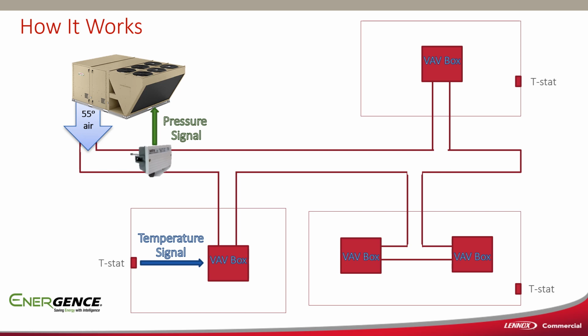While that's happening, we are going to supply 55-degree air out of the package unit, utilizing what we call discharge air control. So our compressors are going to stage up and down whatever they have to do to meet 55-degree discharge air that's being measured in the supply trunk leaving the unit. We also have a pressure sensor, or a pressure transducer, in the supply trunk. And as those boxes open and shut, the static pressure in the ductwork is going to reflect that.